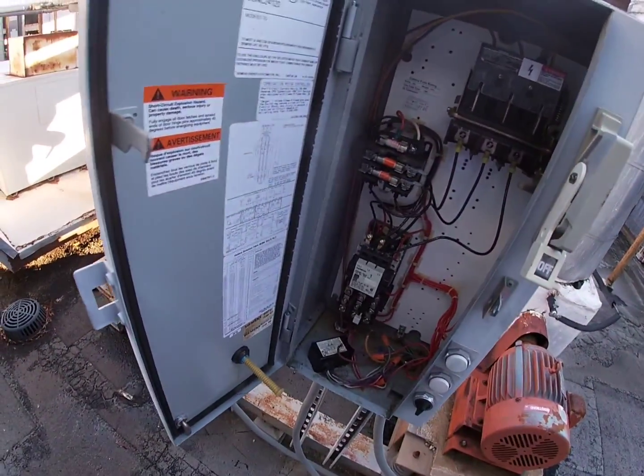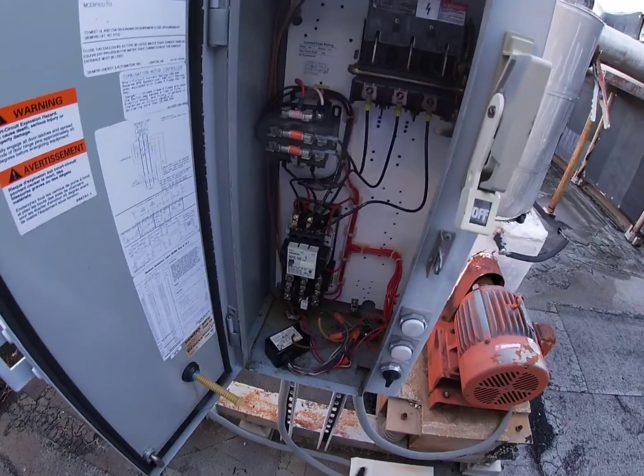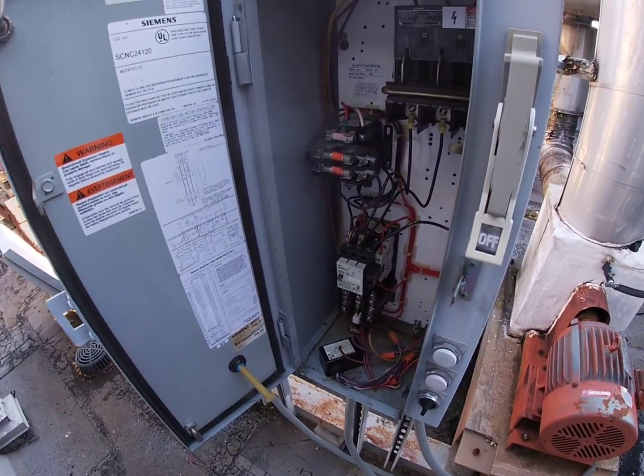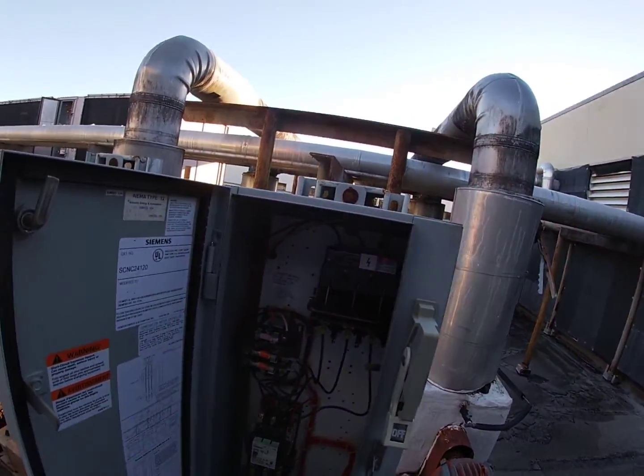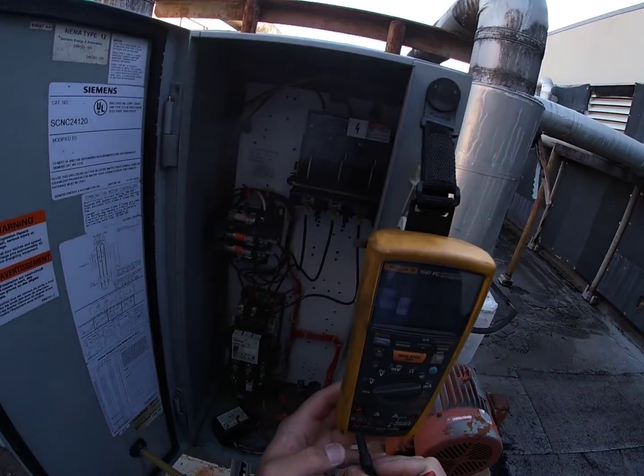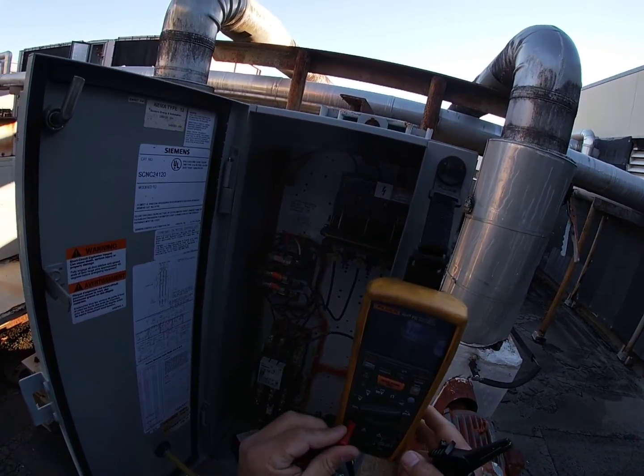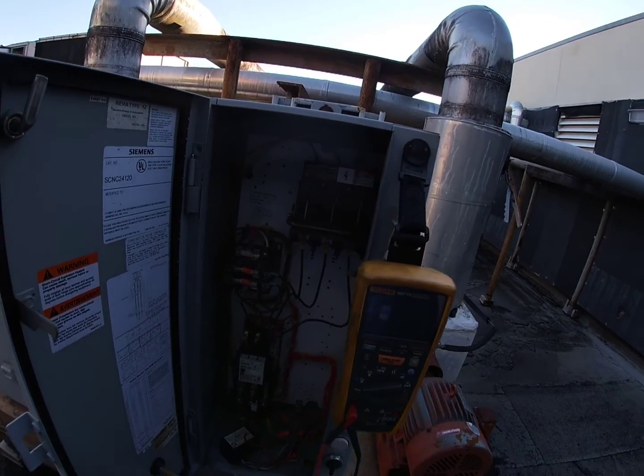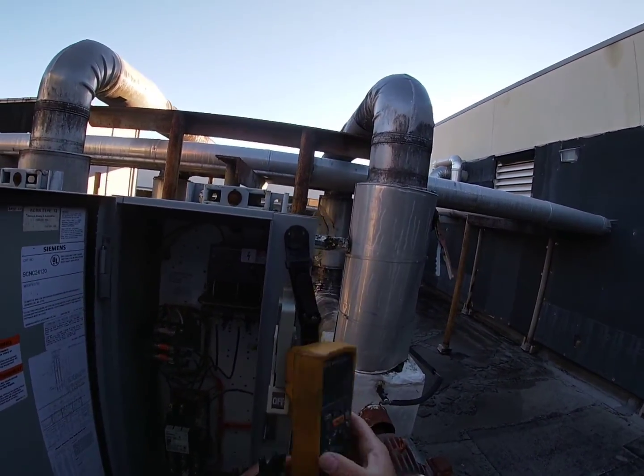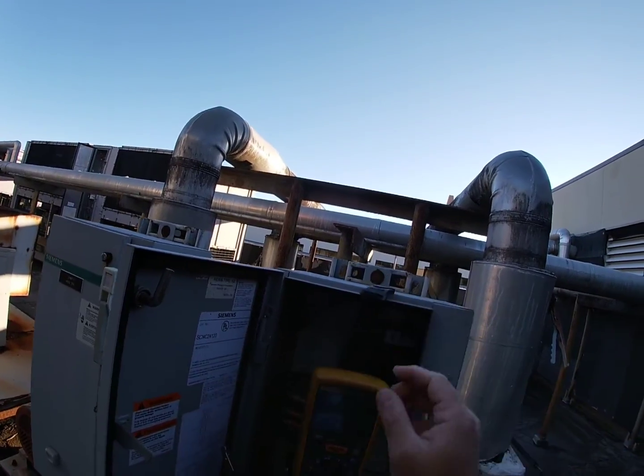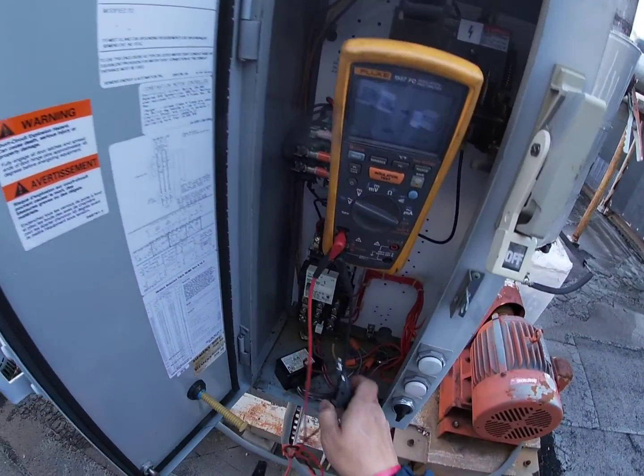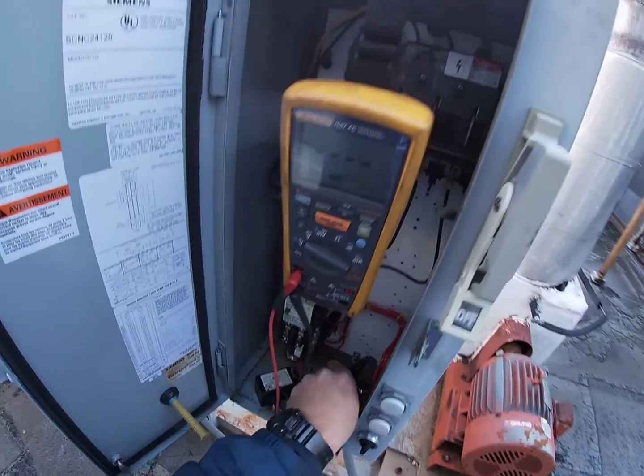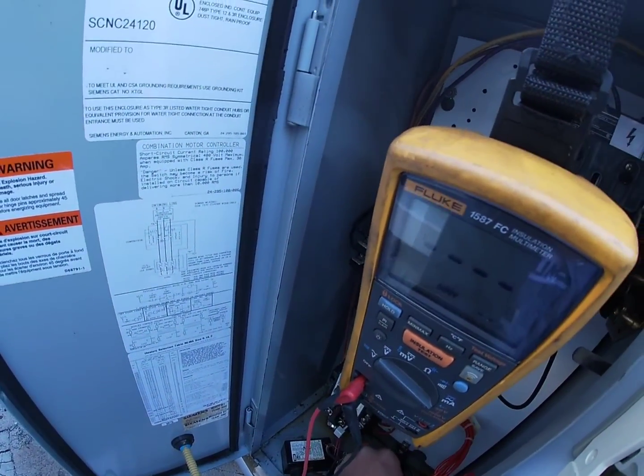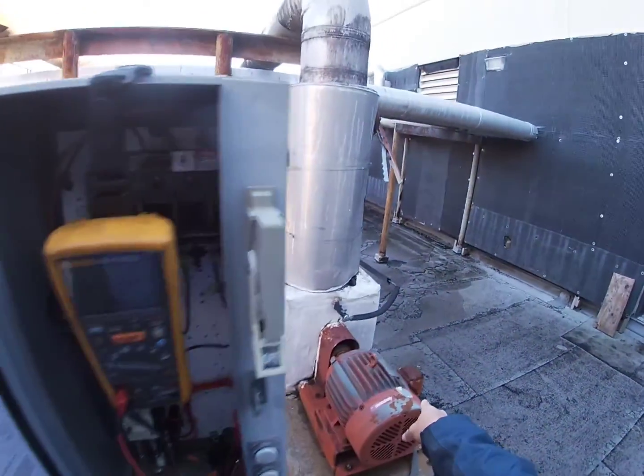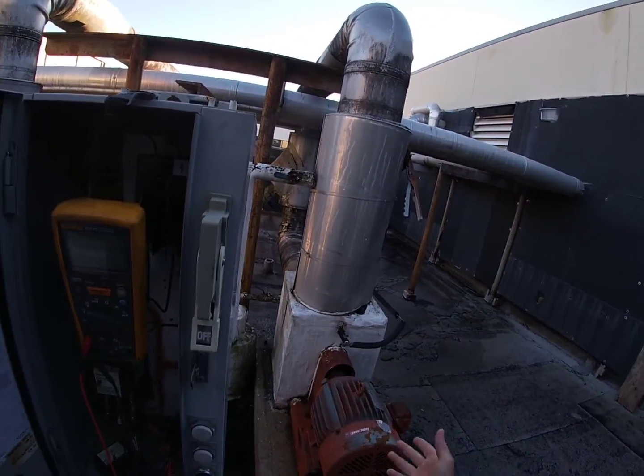I already checked resistance on that motor and it was showing the resistance to be good. So we're just gonna megger it real quick because it did run this way for a little bit. So I just want to be on the safe side and make sure there's nothing wrong with that motor before replacing that contactor there. So put my Megger on here. I'm gonna do 500 volts. So we're at 500 volts. Here, good ground. If I'm bad here, then I'll go ahead and pull the wires off the pecker head and we'll check it straight on the motor.